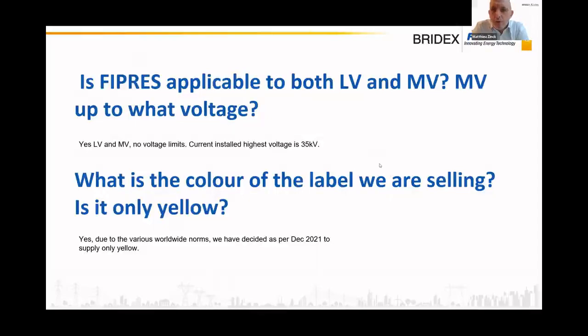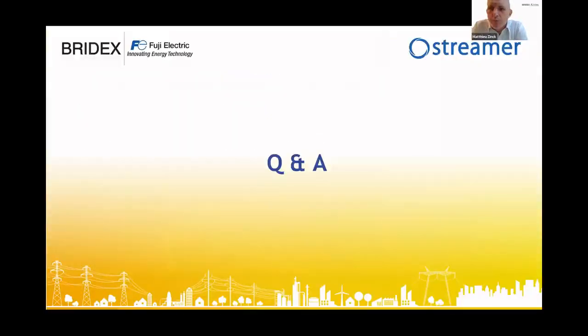Okay, so now we will switch to the questions that were posted inside the chat. One of the first questions is what is the difference between the new FPA and the old FPA? Basically, on the new FPA we have reinforced the EMC capabilities. We have added the front display that allows you to set the thresholds, or the volume of the compartments, by yourself. On the former FPAs, the threshold was set at factory level, and you would buy an FPA according to different compartment volumes. Now with the new FPA, you set up the volume of the compartment by yourself, which is more flexible on site to readjust things.